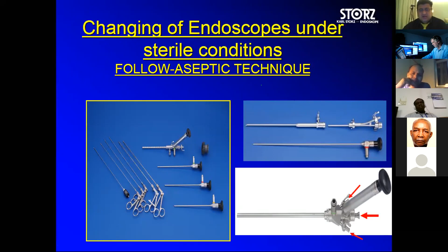Surgeons have been using the endoscope for quite some time, which is good, but sometimes it's good to know the anatomy, how this endoscope is made. I will share a short video of how it is prepared, but in a nutshell, there are two shafts, one inside the other. Inside the inner shaft we put a series of rod lenses, and between the shafts there is some space left where we put hair-like fiber bundles. Finally, these light transmission fiber bundles, which are white in color, come out and are engraved at the light cable attachment.